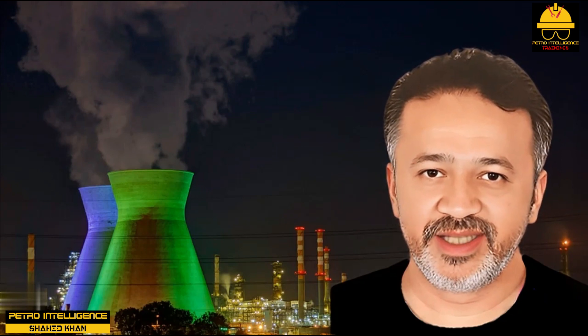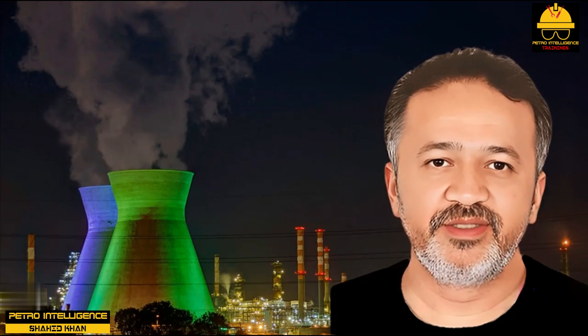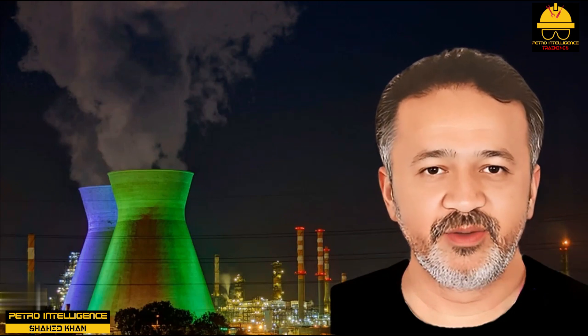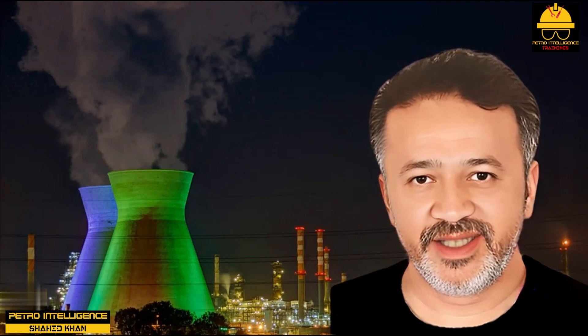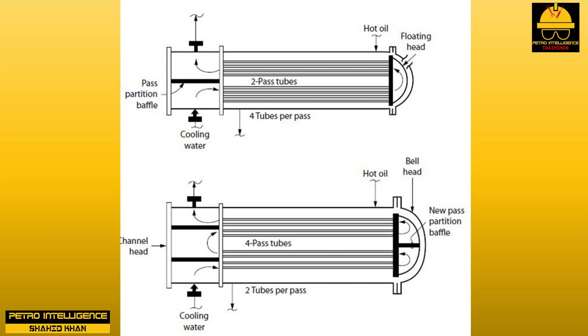One mistake I have made in the past is confusing the effect of trapped air with fouling, especially on startup. Air may be trapped both above and below the pass partition baffles. The air can fill some of the tubes — especially at lower tube velocities — and effectively reduce the exchanger surface area. Opening the vents on the channel head to vent out accumulated air is a good method to restore lost cooling capacity.